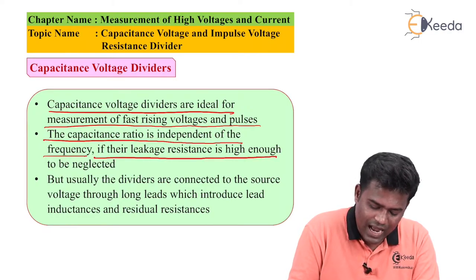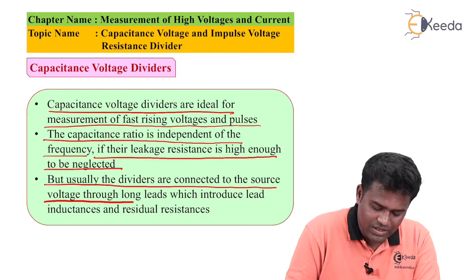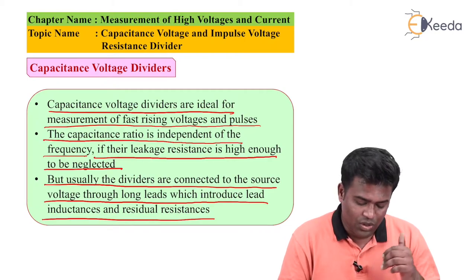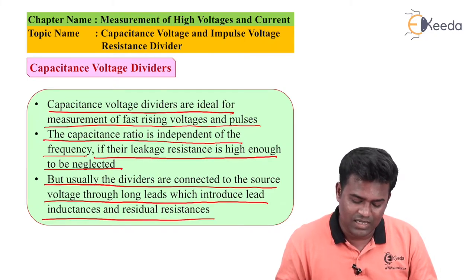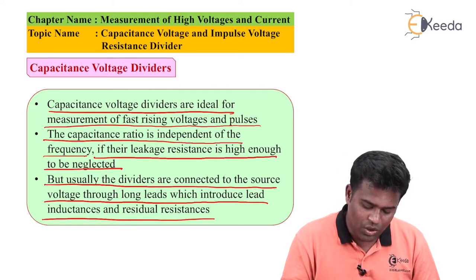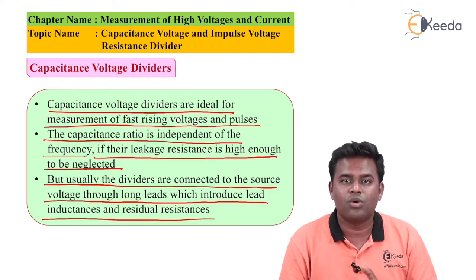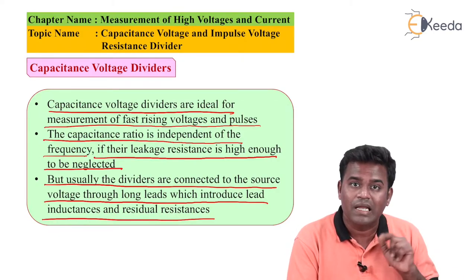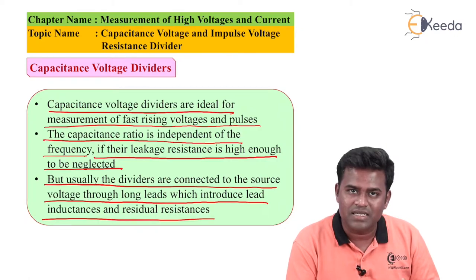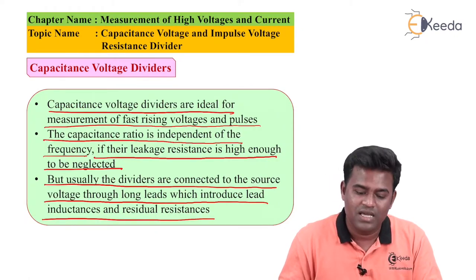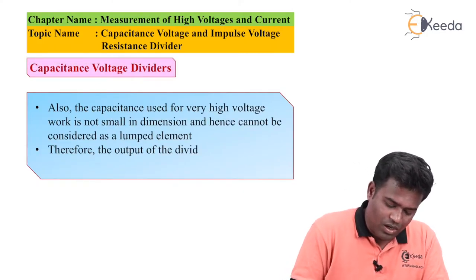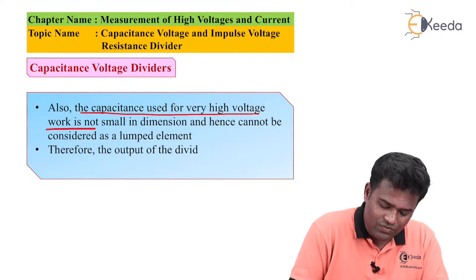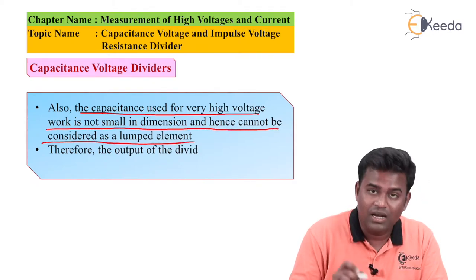If their leakage resistance is high enough to be neglected, usually the dividers are connected to the source voltage through long leads which introduce lead inductance and residual resistances. This applied voltage will include inductances in the system and residual resistances in the system. The capacitance used for very high voltage work is not small in dimension and hence cannot be considered as a lumped element.